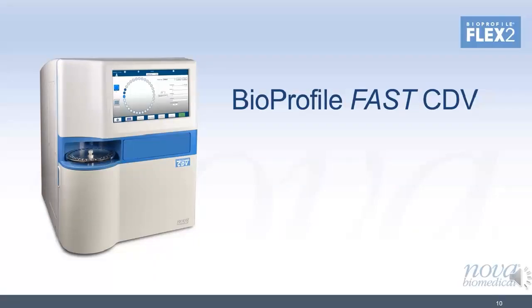BioProfile FastCDV has a throughput of 45 samples per hour and an analysis time of just 82 seconds. But more importantly, the time between the dilution step that the instrument performs and the analysis beginning, the processing of the images, is less than 15 seconds. So again, it completely eliminates any osmotic shock that you would observe if you had to pre-dilute your sample, and the amount of time that the sample sits in that diluent can drastically impact the accuracy of your results.